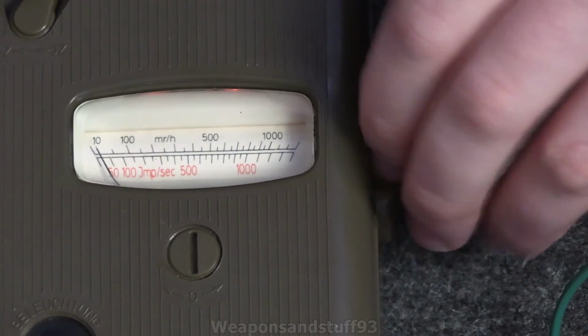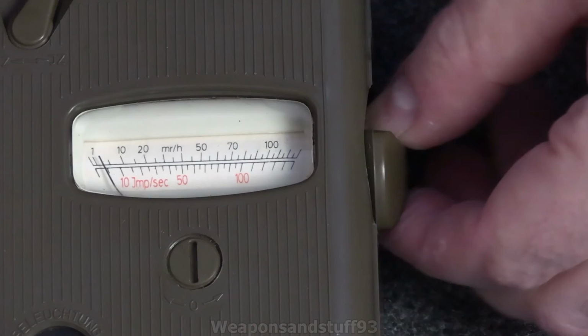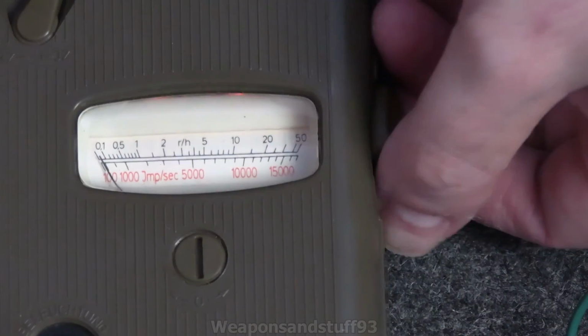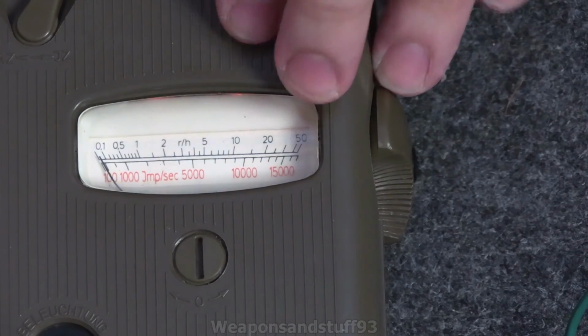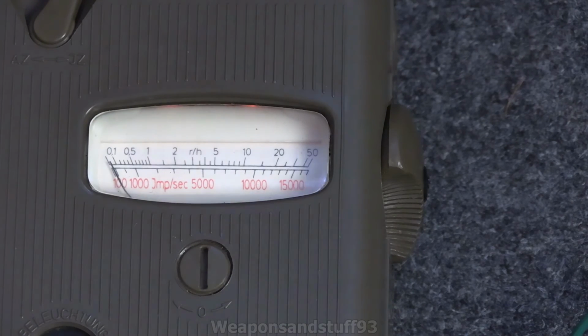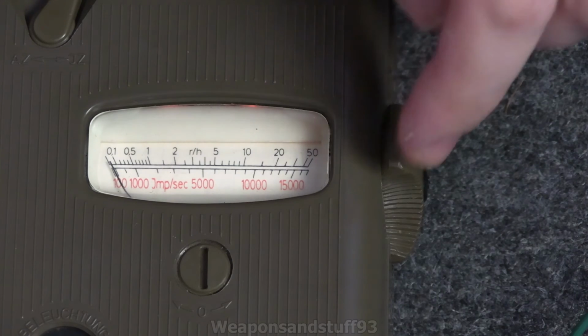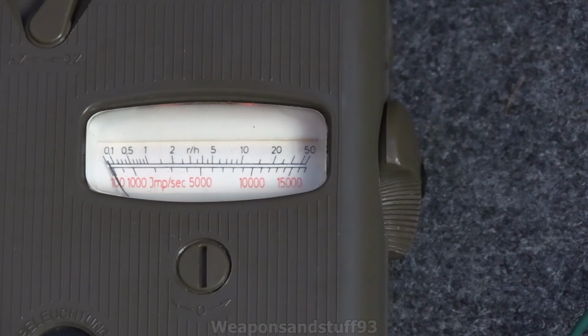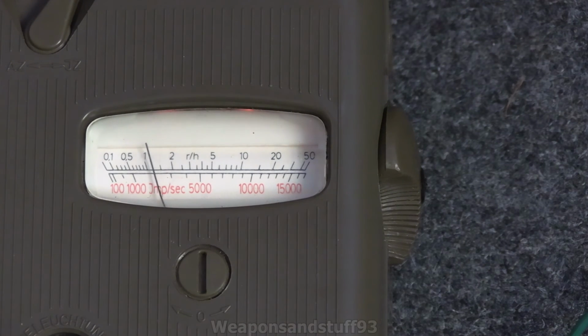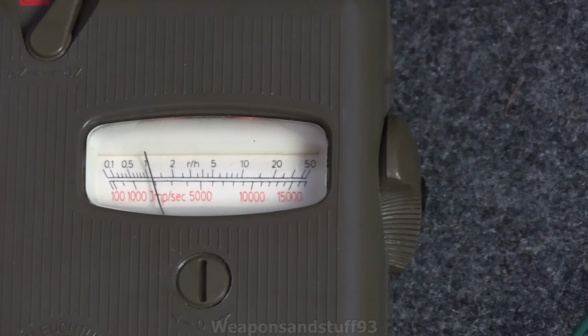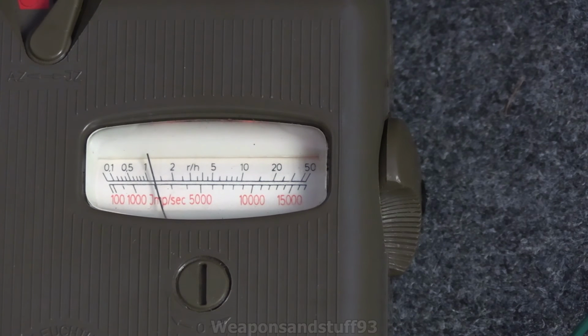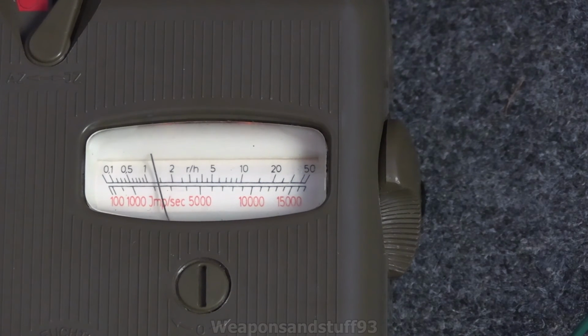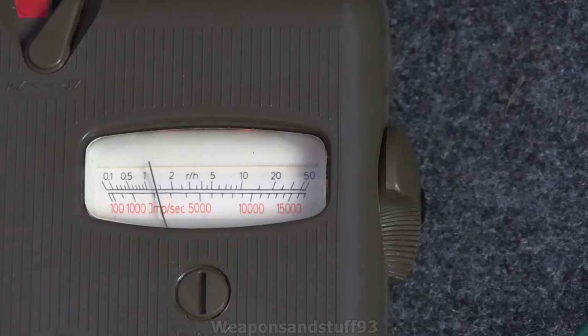Yeah. And the highest scale, and again this is beta radiation, not gamma, because again the Roentgen scale is actually designed for gamma and X-rays, not beta radiation, but it still gives you an idea of dose. You're meant to be using the counts on this for the other part, but here we go. Now that actually is a very accurate reading for this, because it's just over 1 Roentgen, which is what an ionisation chamber tells me this check source is.